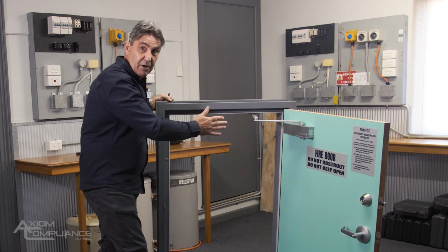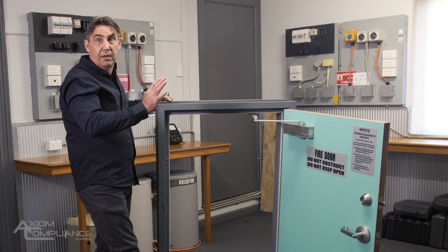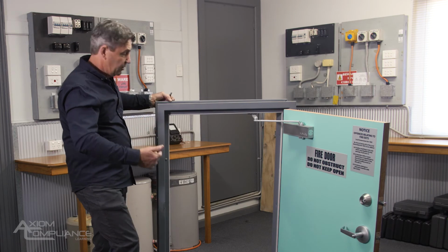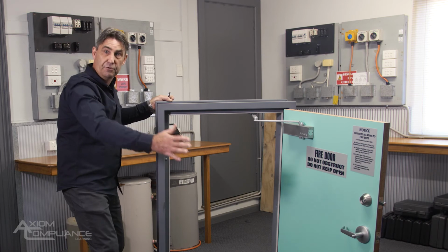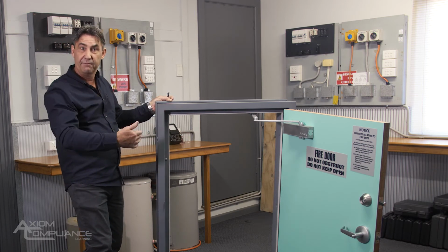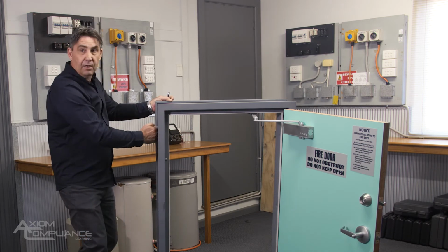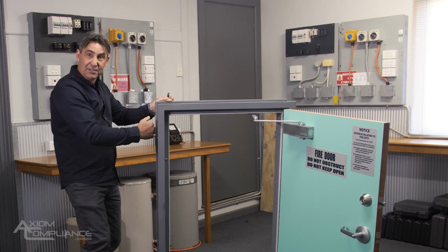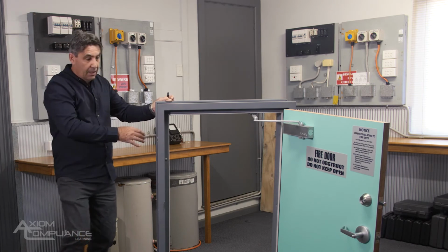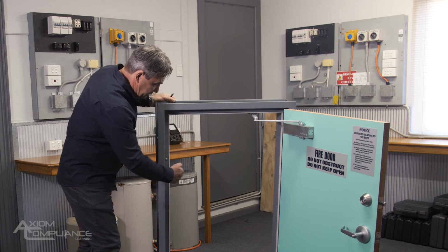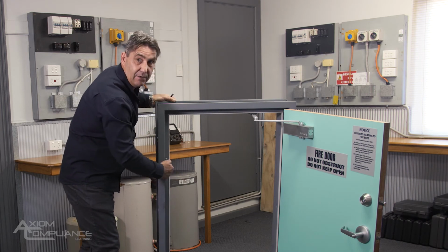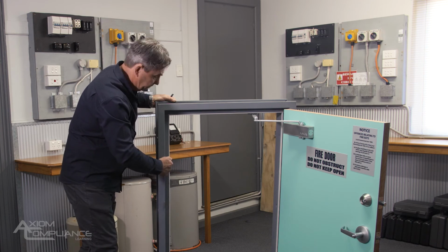It's been tagged as a fire door frame by somebody, and it's not a fire door frame. Because if I inspect the frame, you think about it, if you've got a fire trying to push through this into an exit that people are trying to escape from, you don't want smoke or fire coming around these edges here, because you've got a wall here. And also, you don't want fire or smoke coming in and around these closing points, all right?